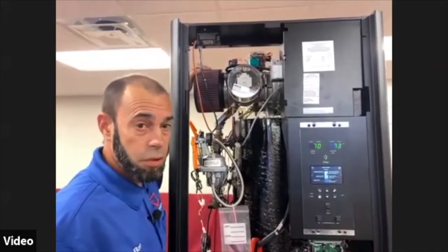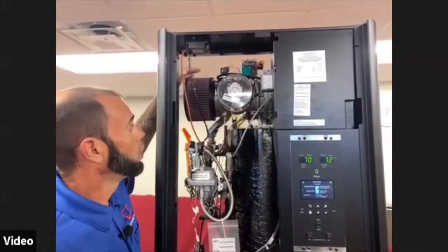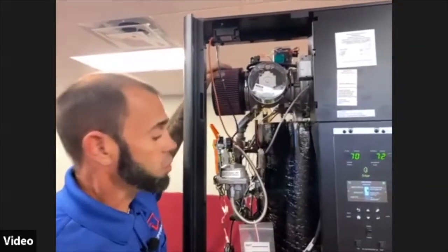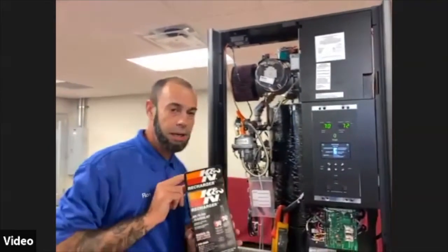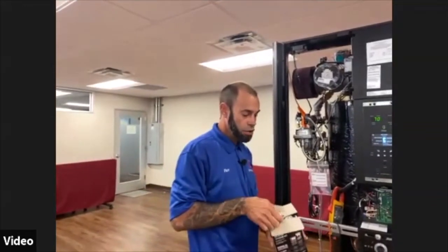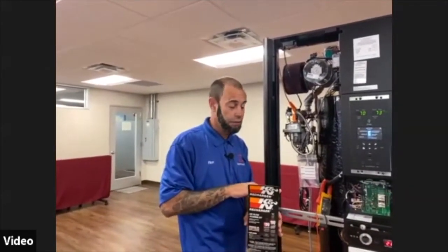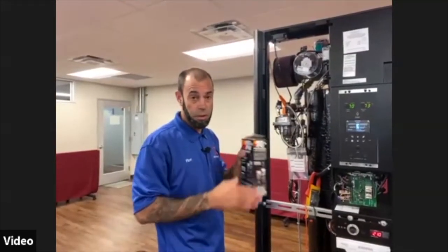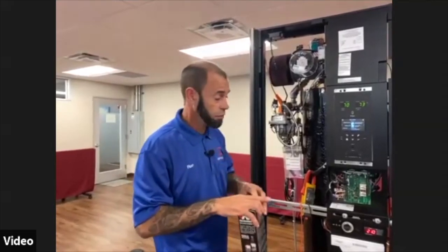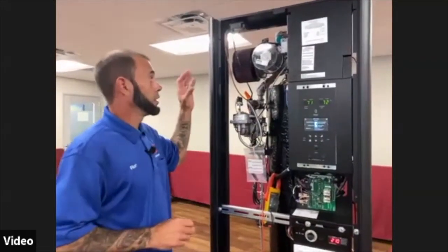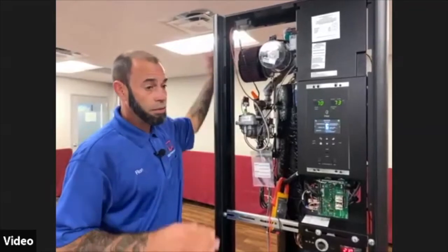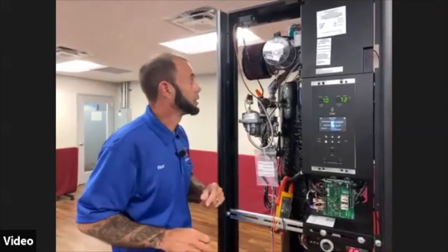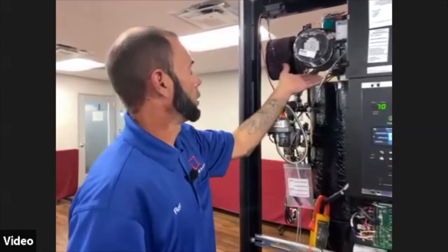This filter is serviceable, cleanable, washable, replaceable. So a couple things with that. If you're going to take it and clean it, K&N makes a recharge kit, and the recharge kit actually has the cleaner and the oil in it. This is a process, and you'll want to let the filter dry completely, 100%, before putting the oil on it and reinstalling it back onto the boiler. I recommend having a second filter just in case. You can replace it, install it, take this one out, clean it. Next time you need to replace it, you already have it ready to go. So that's connected to our air fuel valve.